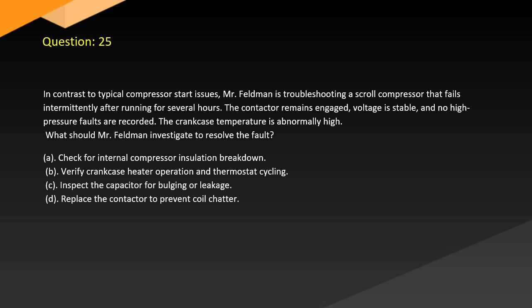A. Check for internal compressor insulation breakdown. B. Verify crankcase heater operation and thermostat cycling. C. Inspect the capacitor for bulging or leakage. D. Replace the contactor to prevent coil chatter.